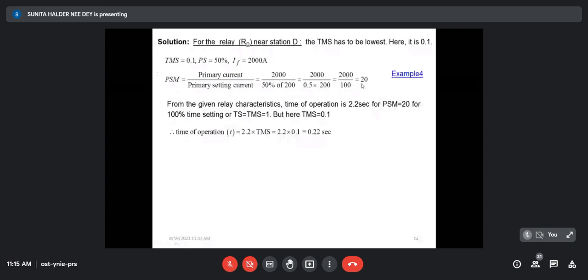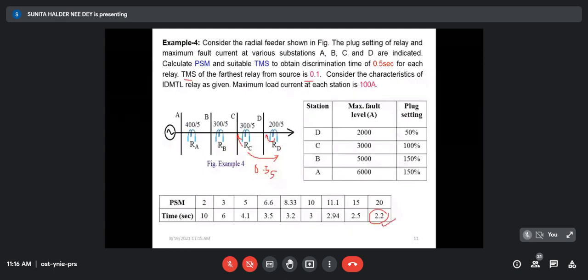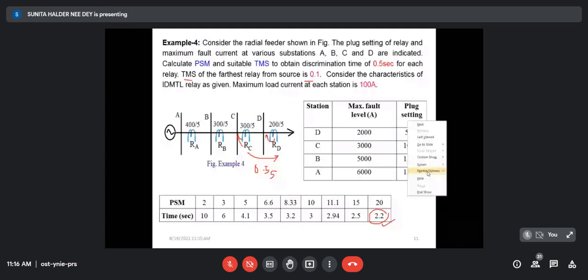If PSM is 20, then from the relay characteristics corresponding to 20, the operating time is 2.2 seconds. The relay should operate at 2.2 seconds. The TMS of the farthest relay is given as 0.1. That means if TMS were 1, operating time would be 2.2 seconds, but since TMS is 0.1, the actual operating time will be 2.2 × 0.1 = 0.22 second.